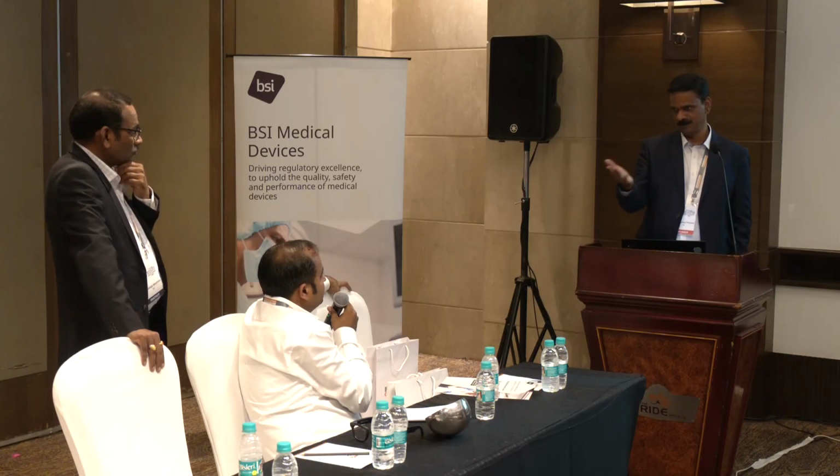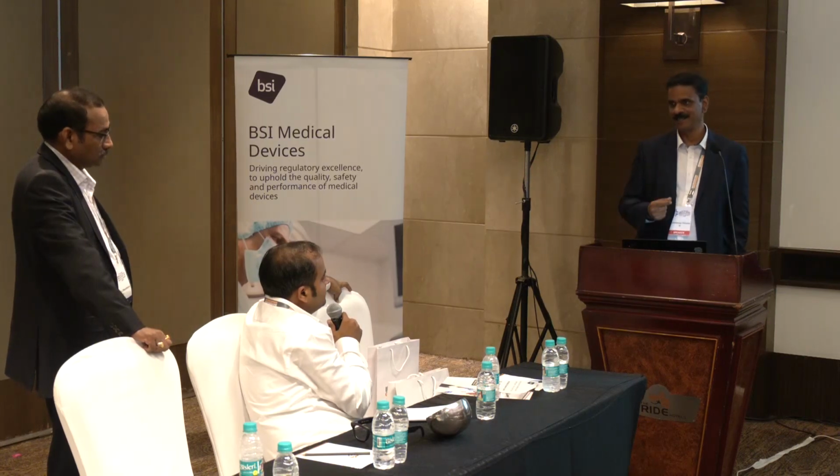For another notified body, I cannot comment on whether they accept it or not. But we do tell manufacturers to refer to MDCG 2020-6, and it says for the lower classification devices, if there is no evolution in the design, it is a well-established device and the state of the art is maintained, then we will accept data from this device.